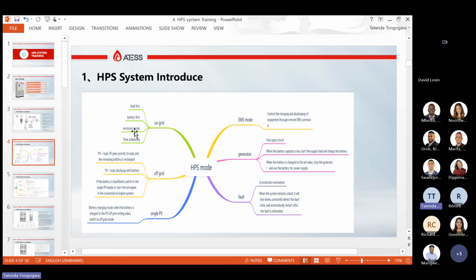Economic mode, during your peak hours, you don't use grid, and then you can charge your battery maybe in the evening when you are not in peak mode. And then battery first, this is more like a backup. Your battery will stay charged, and then in the event of load shedding, you can make use of your battery, like the storage. And then load first. In load first, your PV will supply the load first, and then the remainder is used to charge the battery.